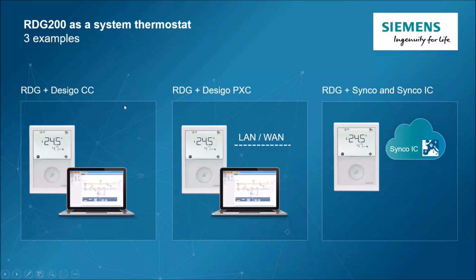But it's also compatible with some of our Siemens systems. You can integrate those devices via KNX into our BMS, building management system, Desigo CC. I will show you this example just a little bit later. You can also integrate our device through KNX into our DesiGo system. So if you have a big plant and you have some primary controllers, some boilers, some air handling units to manage, you can also link our thermostat to those systems. Last but not least, we are also compatible with our KNX Synco system and Synco IC. If you are more aware of those solutions, we are still compatible with them.